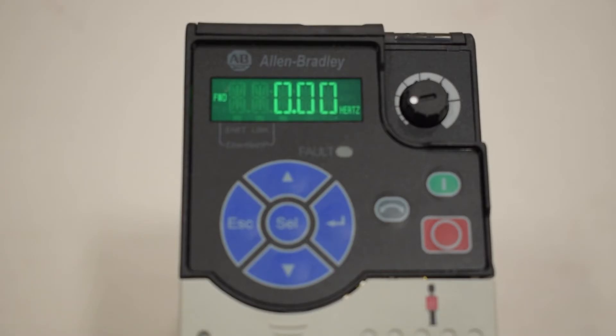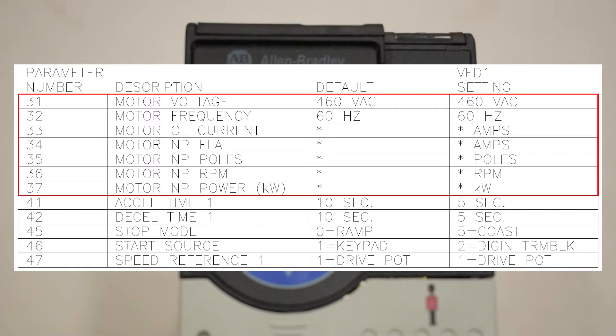Navigate to the VFD parameters table on the LMEC control drawings. The parameters that are marked with an asterisk will need to be set up by the startup technician. These values need to correspond with the provided motor nameplate.